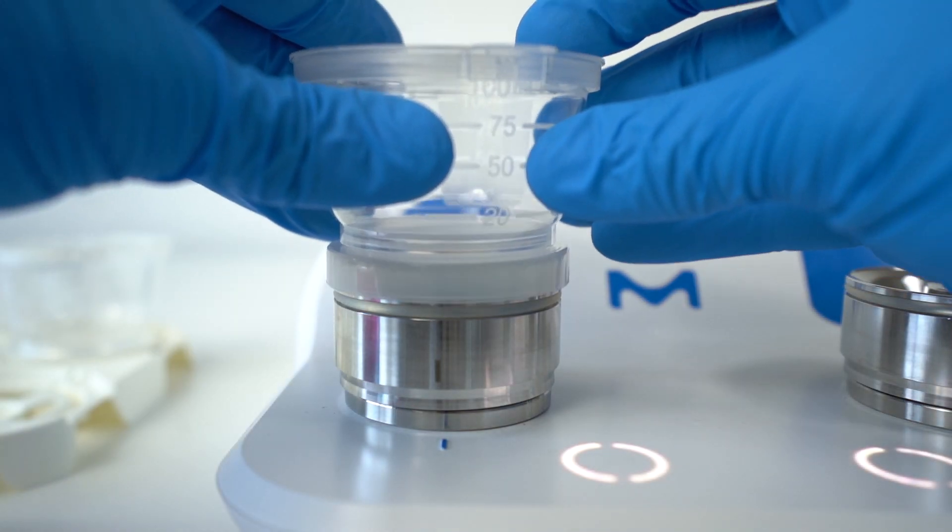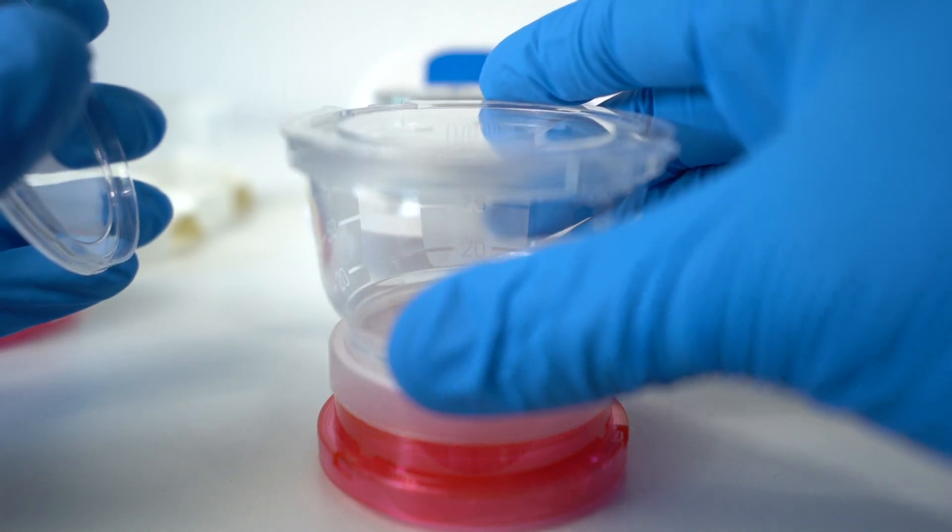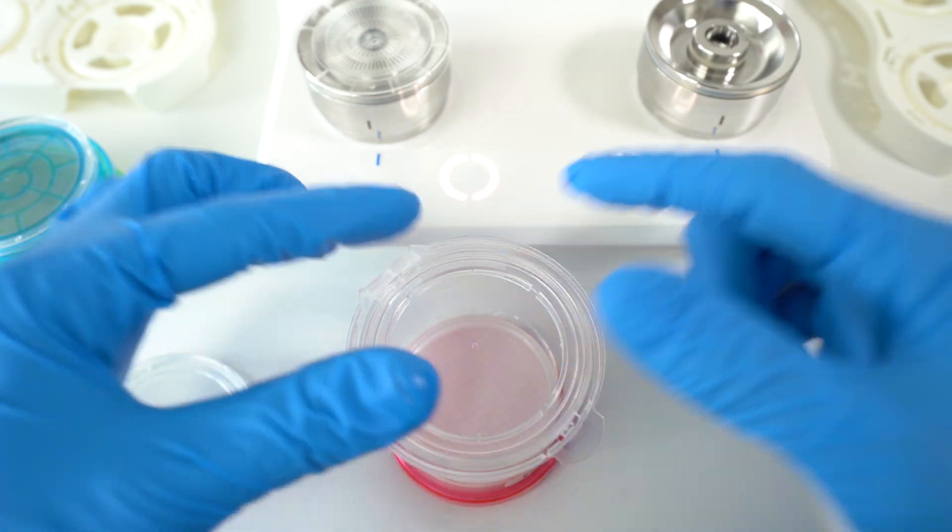And against competition, the Oasis is again a step ahead — before, you were already the leader on the market. The system has been really improved. It's still an all-in-one filtration system, really easy to use and easy to set up. We have kept what we had already with the Milliflex: the membrane which is sealed to the funnel. This is really key because it prevents any bypass of the liquid you are filtering, enables a touch-free membrane transfer to the media, and reduces the risk of having bubbles because the contact between the membrane and the media is optimum — we get a convex shape of the membrane due to this sealed design.